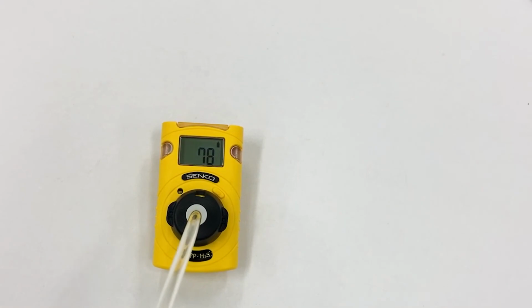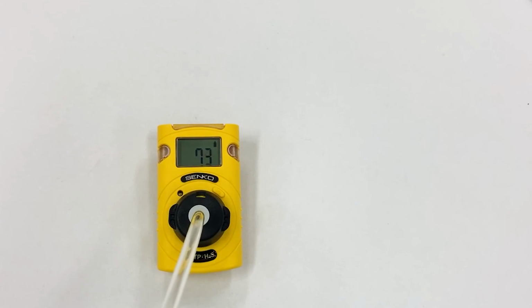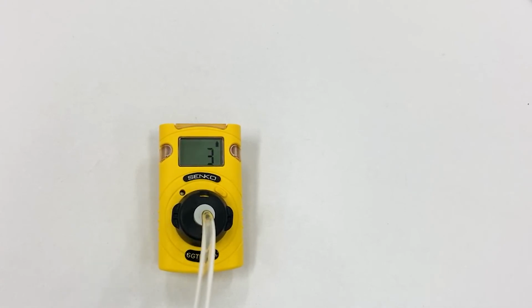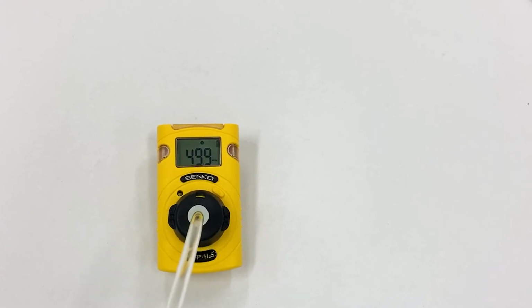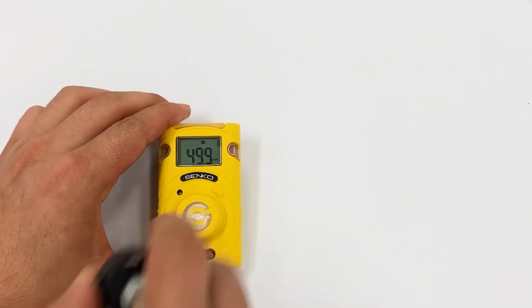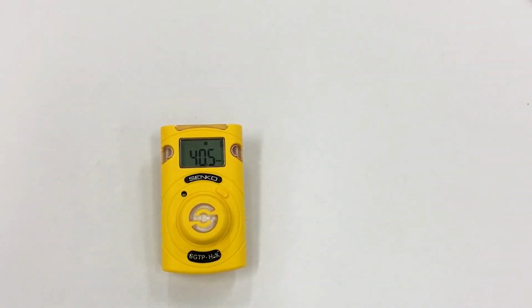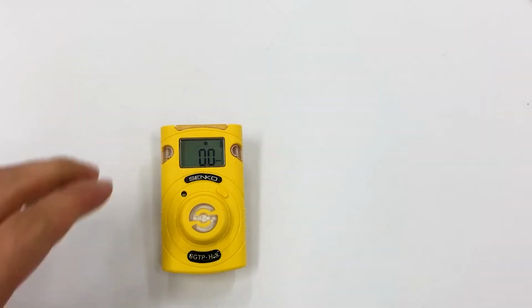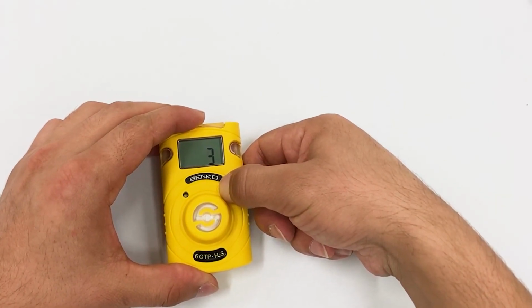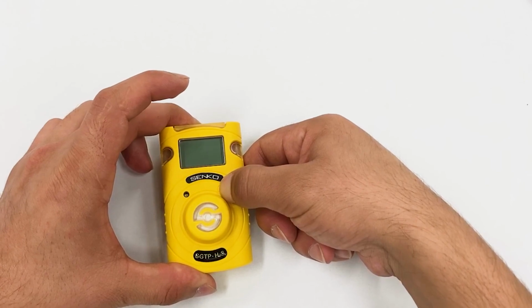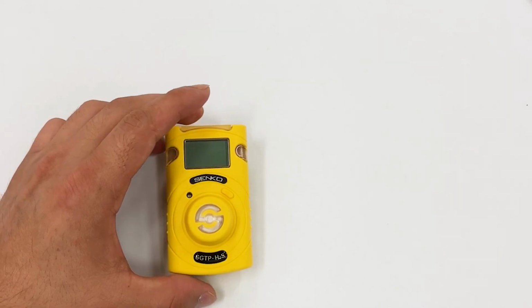It will take 90 to 150 seconds to perform a full span calibration on the sensor on this unit, depending on gas type. As you can see, the calibration has completed successfully and the sensor is ready to perform. Now we can remove the gas calibration cap and we are back in normal operation. The instrument stabilized and came back down to ambient condition. So to turn the instrument off, press and hold the button for 3 seconds. So this gives you an overview of the standard Senko SGT-P instrument operation.